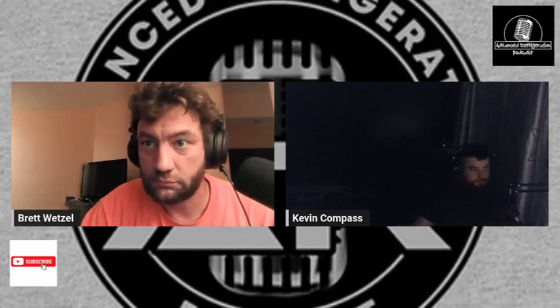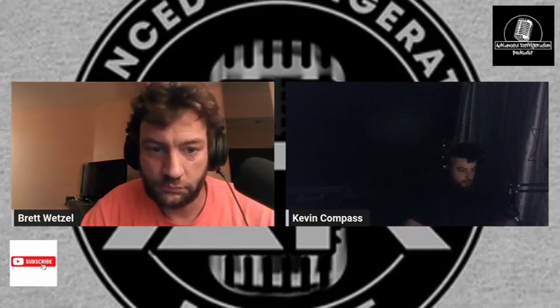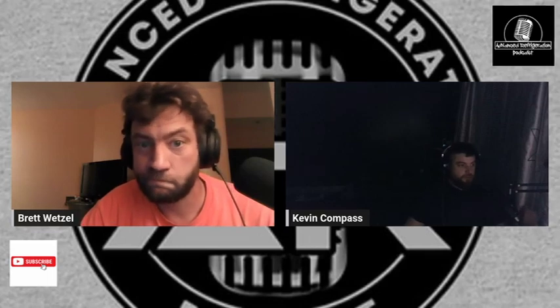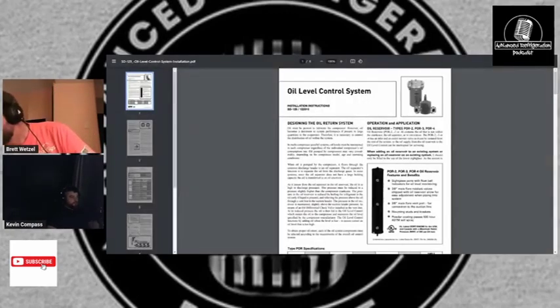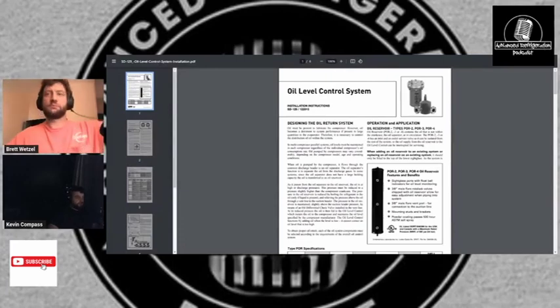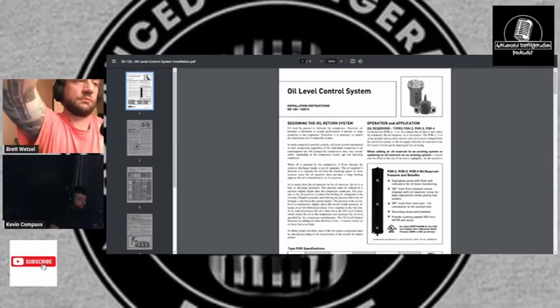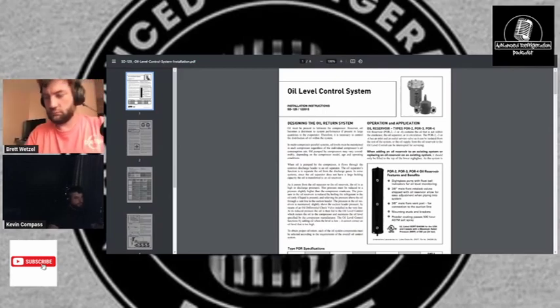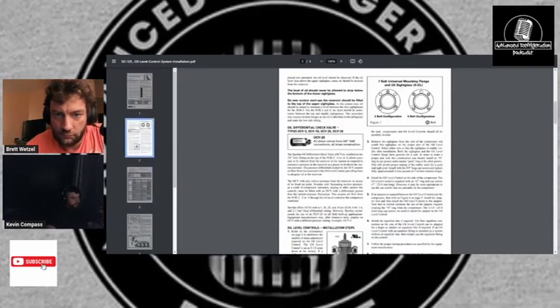So at the top of the oil float is a stem that you set. As you crank it in, you are lowering your oil level. As you back it all the way out, you're raising your oil level. Now, you can predict what it's supposed to be. If you look at the Sporlan chart or the Henry chart, they all have a chart that lists how many turns from top dead center you have and what oil differential pressure you have equals what the level in the compressor is going to be. It's almost dead nuts on.